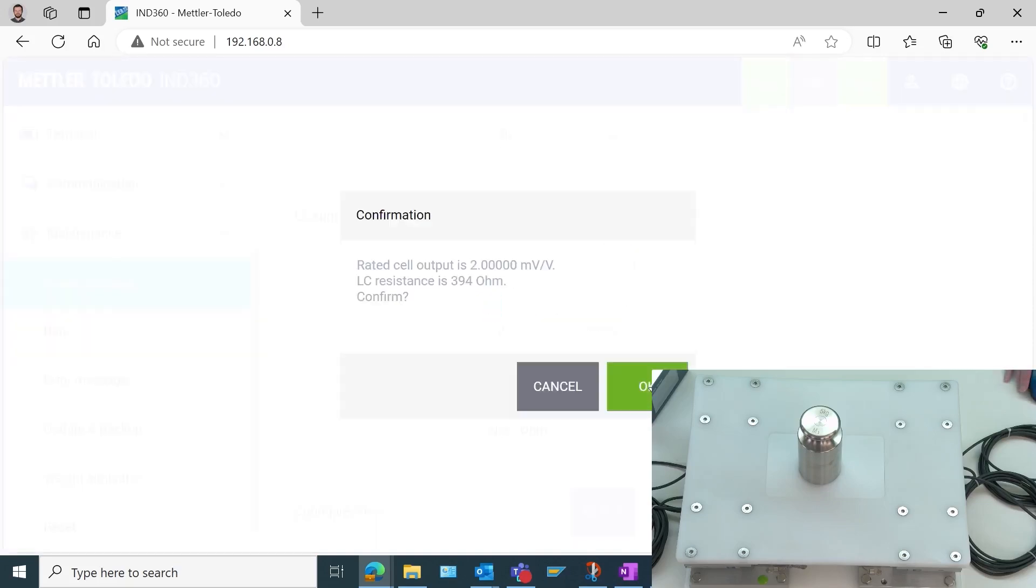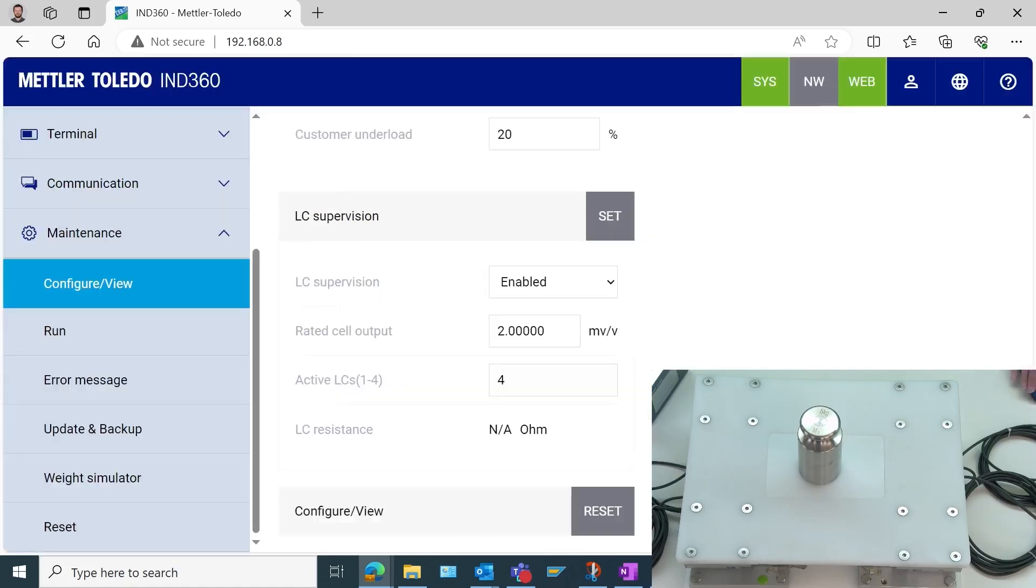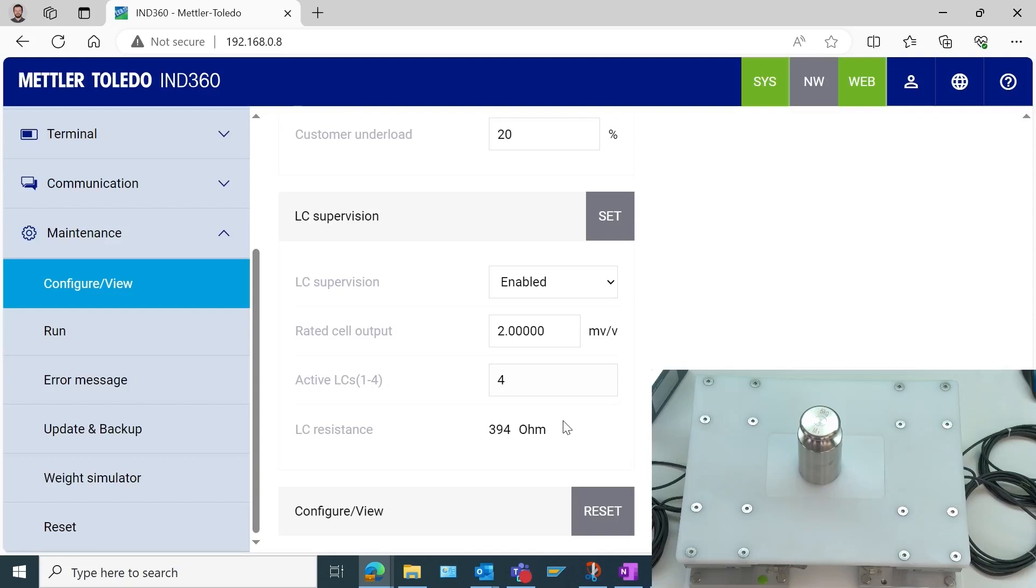So it's going to read what the load cell resistance is. Now we can see it gets a reading of 394 ohms on these particular load cells. You may find different values for you as long as your load cells are connected correctly. You should be able to proceed with this value. So we'll select okay. Now it remembers this. So if there are any sort of disconnections of those load cells, that will now be an error and it will be able to tell us which load cell is disconnected.